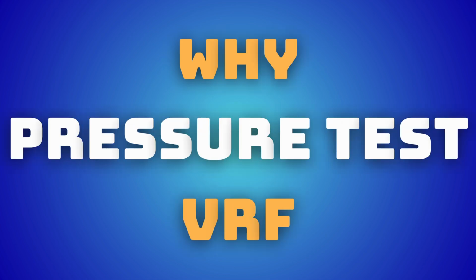Pressure testing and leak searching, it's not a fast process, and don't fall into the trap of feeling like you have to hurry because it's taking so much time and the customer's on your back, your boss is on your back. So what are some situations we're going to be pressure testing in, and why is it so critical with a VRF? First, it comes back to just, we think we've got a low charge.